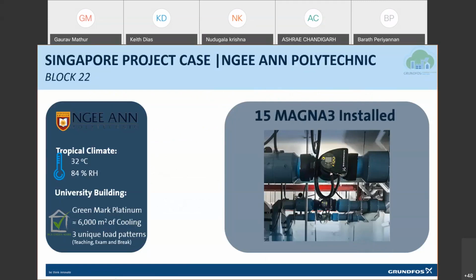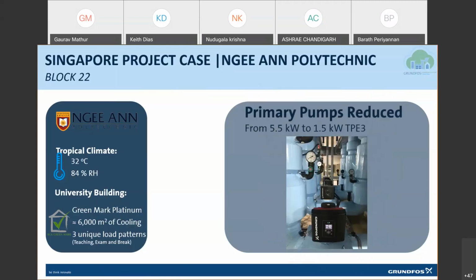This is Ngee Ann Polytechnic. It's an educational institute. It is a gold-rated green building. It's a platinum-rated green building already by the time when we reached and did the audit there. And after the audit, when we implemented the distributed pumping system there, we installed around 15 Magna pumps. This is the circulator pump. And we changed the primary pumps, and you can see the size of the pump has reduced from 5.5 kilowatt motor size to 1.5 kilowatt pumps.